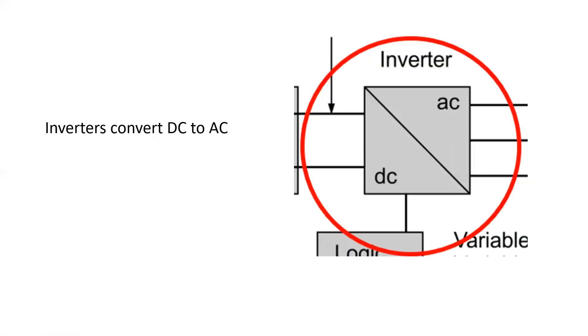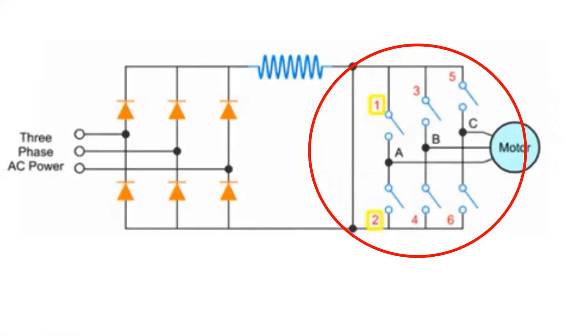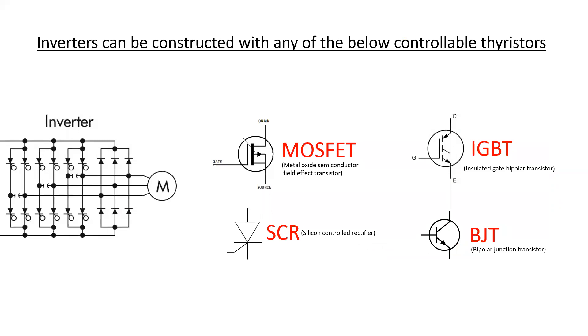Inverters convert DC voltage to AC voltage using a number of different types of electronic devices. Essentially, if we simplify the process, an inverter section is a series of six switches. Depending on which two switches are closed at any given moment, that particular line is energized. Inverters can be constructed with any of various controllable thyristors, all having different gate controls that allow them to turn on and conduct, then turn off or commutate, producing small or long bursts of DC voltage.